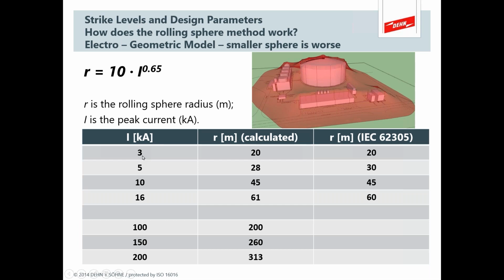If you need to withstand very modest lightning, that's a low current, and a low current means a smaller radius. Remember, we're talking about controlling risk. If your risk is average, we consider a 10 kA pulse, which corresponds to a 45 meter rolling sphere. You see equivalence in other standards too, like NFPA using 150 feet, approximately 45 meters, for their rolling sphere radius calculations. The standards are fairly well aligned for what we'd call the normal industrial risk category.